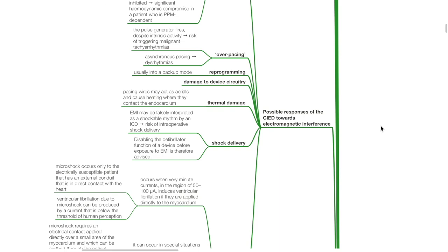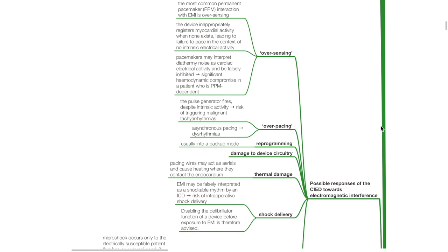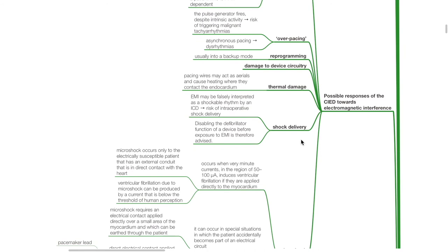Potential responses of the CIED towards EMI: oversensing is the most common permanent pacemaker interaction. The device inappropriately registers myocardial activity when none exists, leading to failure to pace in the context of no intrinsic electrical activity. Pacemakers may interpret diathermy noise as cardiac electrical activity and be falsely inhibited, which may lead to significant hemodynamic compromise in a pacemaker-dependent patient. Overpacing: the pulse generator fires despite intrinsic activity, risking triggering malignant tachyarrhythmias. Reprogramming may occur, usually to a backup mode. Damage to device circuitry: thermal damage — pacing wires may act as aerials and cause heating where they contact the endocardium. EMI may be falsely interpreted as a shockable rhythm by an ICD, resulting in the risk of intraoperative shock delivery; disabling the defibrillator function before exposure to EMI is therefore advised.